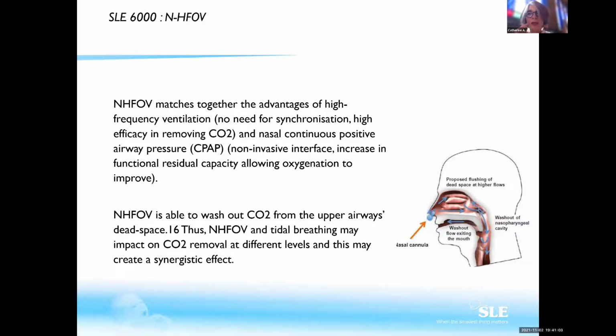One of the important parameters is a washout of your upper airways. So when you have a high flow nasal cannula, what do you do? You push some fresh gas here, which will chase away the CO2, the gas which was coming from the last expiration and which was staying in your upper airway. So you will chase this gas by some fresh gas. So whenever your patient starts a new breath, you start with some fresh gas and you don't have any CO2 rebreathing that was due to the gas that you had staying in your upper airways.